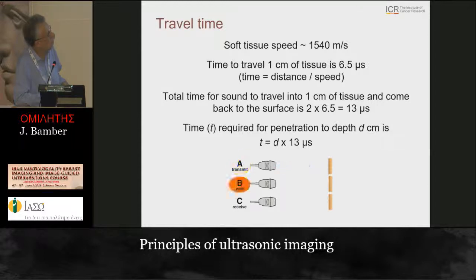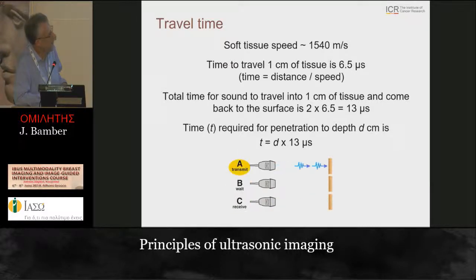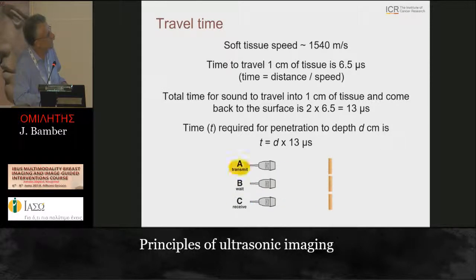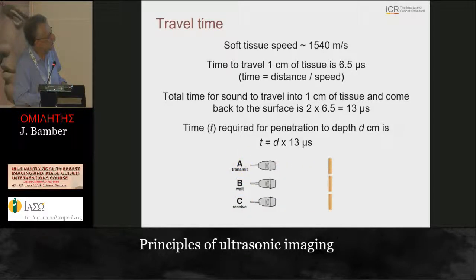When the echo comes back from the deepest region, you can send out another pulse for the adjacent image line. If you don't wait that full travel time, there will be confusion over where the echoes came from. The speed of sound in most tissues is approximately 1540 meters per second, and for one centimeter depth it takes 6.5 microseconds to travel; we must wait for the round trip, so that's 13 microseconds per centimeter depth.